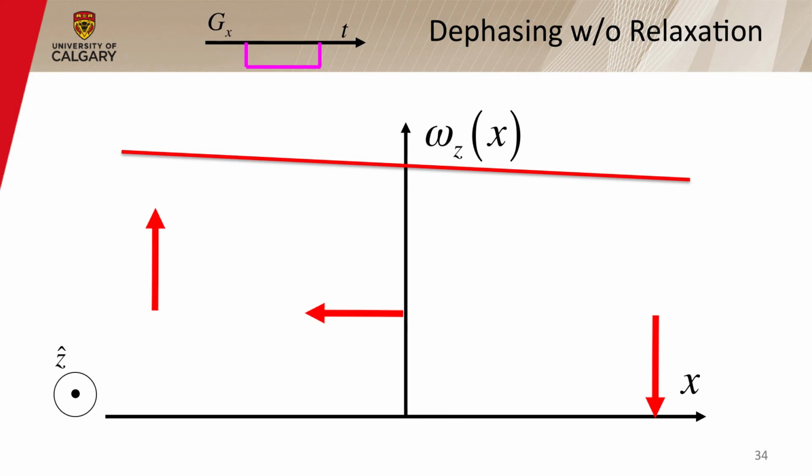We applied it for some length of time, and in this particular case, these spins look like they're minus 90 from our isocenter, and these look like they're plus 90. The reason is that clockwise is negative and counterclockwise is positive, okay?